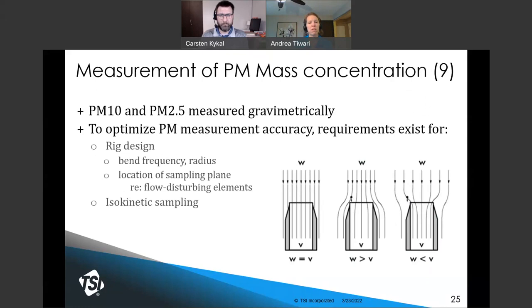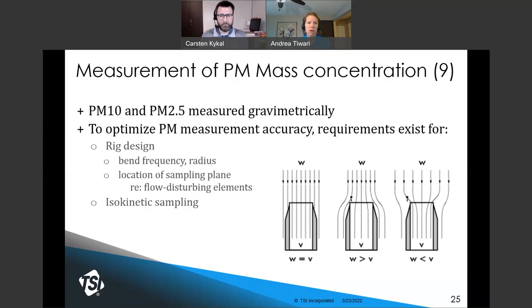Isokinetically means same speed: the velocity of the air entering the sampling tube needs to match the speed just prior to and parallel to that sampling tube — the air velocity in the sampling tube must match the air velocity in the duct. Matching these velocities ensures that larger particles are sampled in a representative fashion, as shown in the left of the three figures. This is important because particle mass data is dominated by large particles. If the velocities don't match, as in the middle and right-hand figures, large particles can either be undersampled or oversampled, resulting in inaccurate particle mass data.